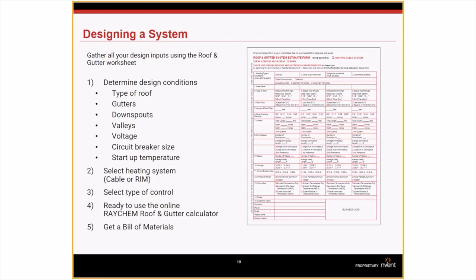Also check whether there are breaker size limitations if the panel doesn't have sufficient room for the full system. Determine whether your customer wants a cable system or a RIM system, and consult them on controller type — ambient control sensing air temperature, or a moisture-temperature controller that energizes the heating cable throughout winter. Once you have all this information, you're ready to use the Raychem Roof and Gutter Calculator to get your full bill of materials.